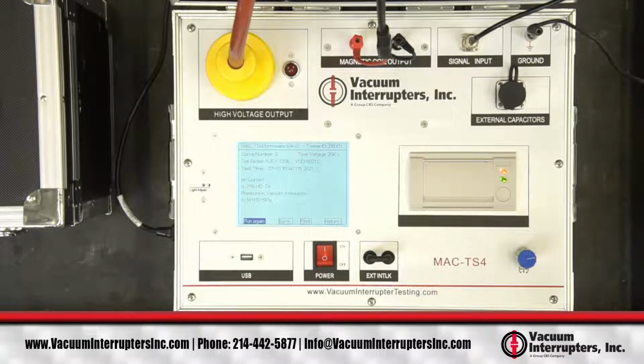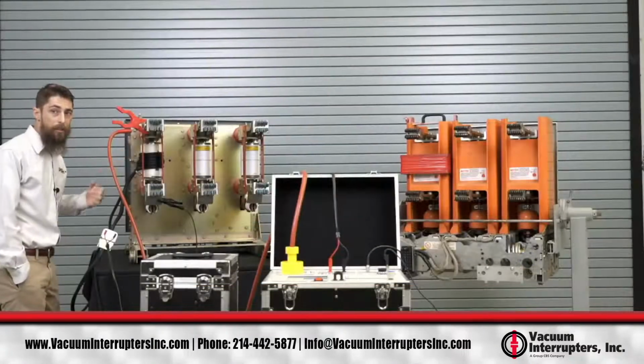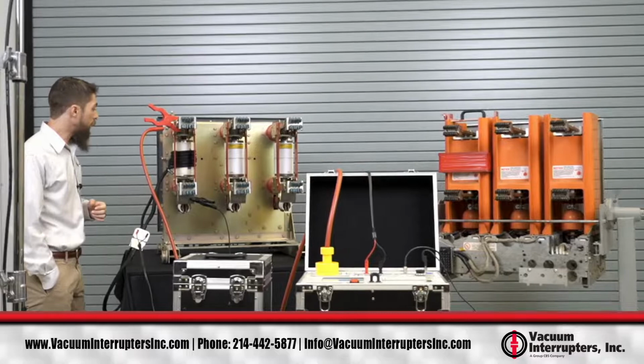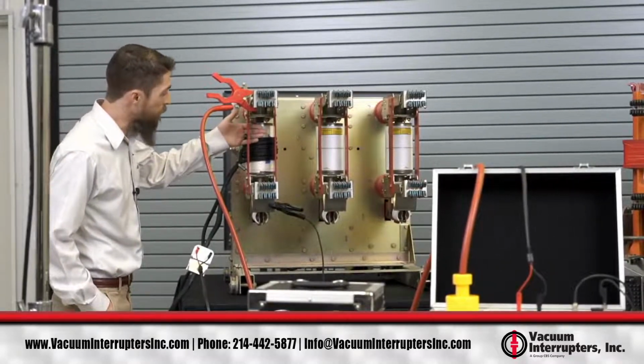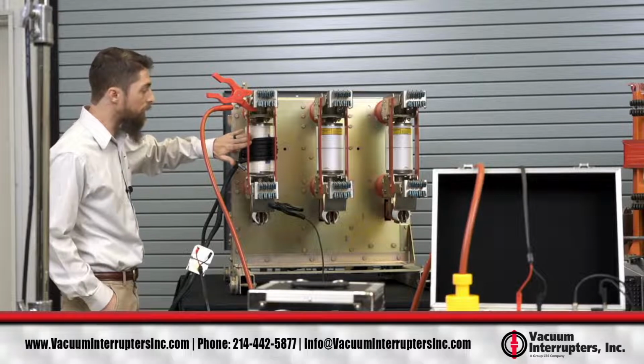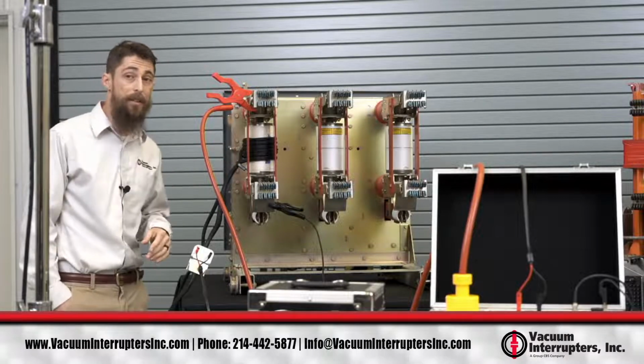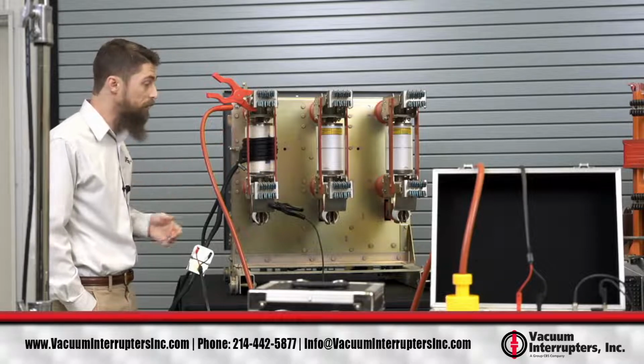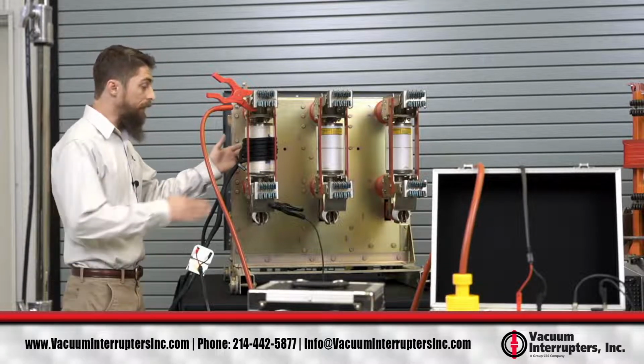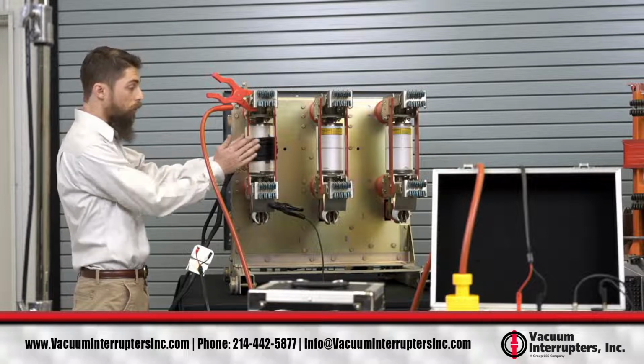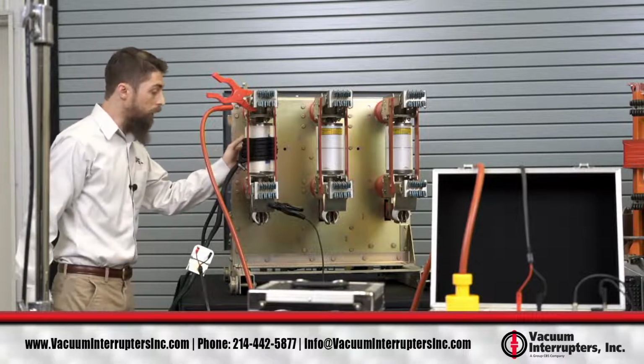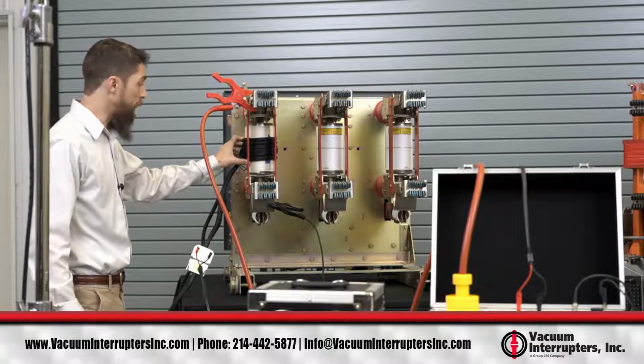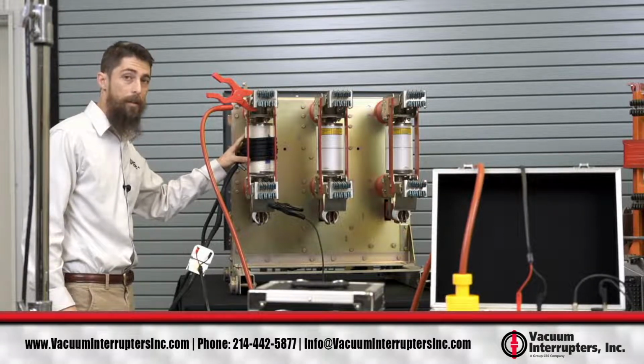That's the basic test for a universal flex coil. The only other thing I have to add is, in this style of vacuum circuit breaker, we have a little clearance to actually wrap this coil and get between the line to load insulators and the VI. In some cases, the VI is too close to these line to load insulators. And in that case, it is okay to wrap the coil around those line to load insulators as well. But only in that case. If it is possible to wrap directly around the VI, then that's what you should do.